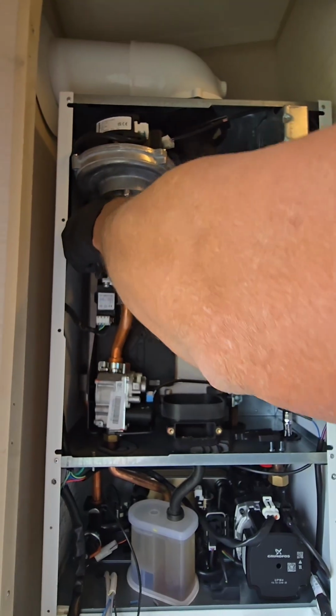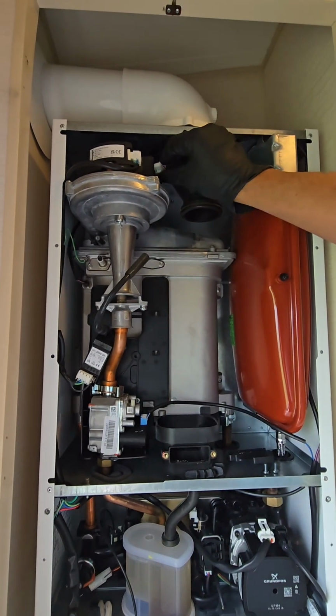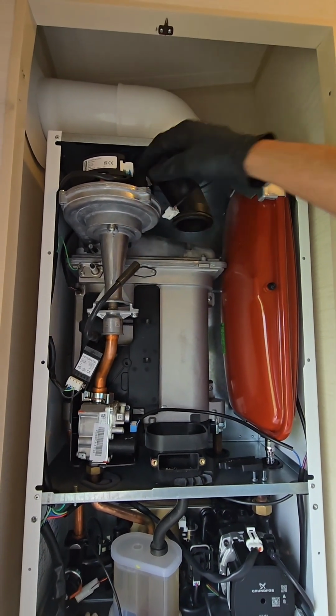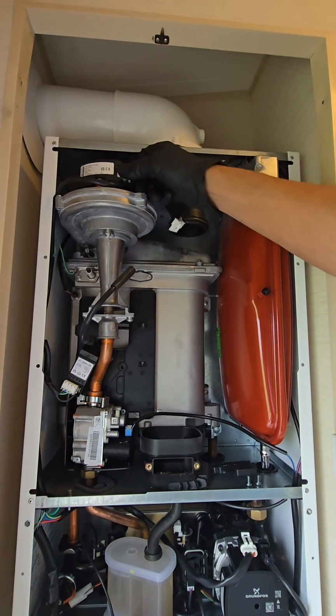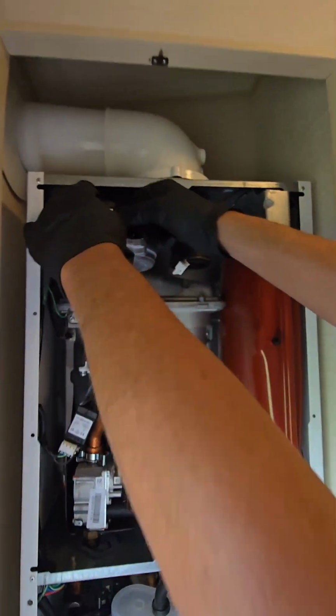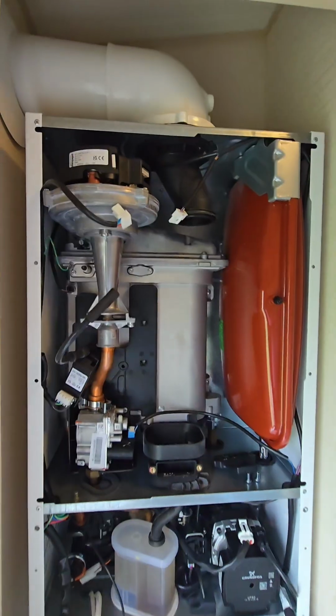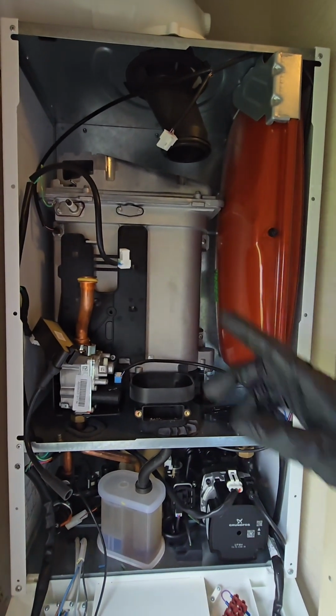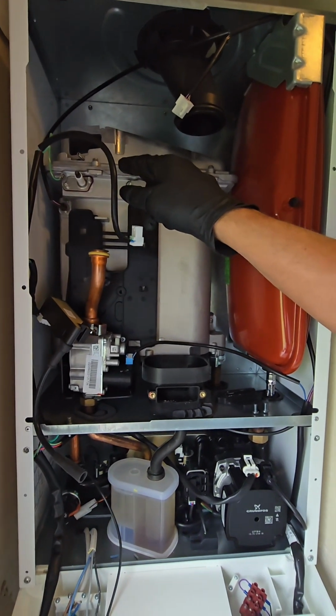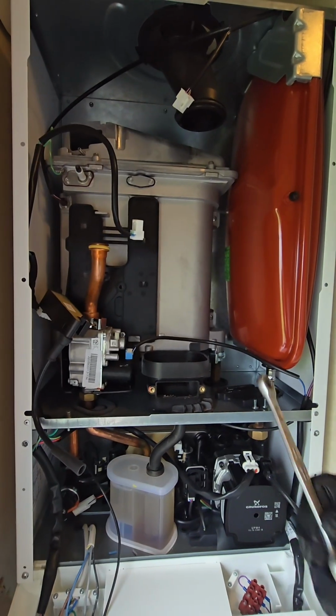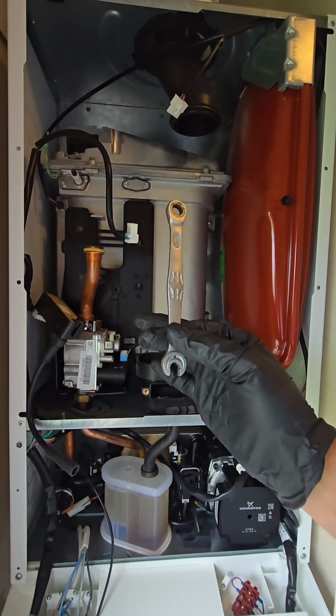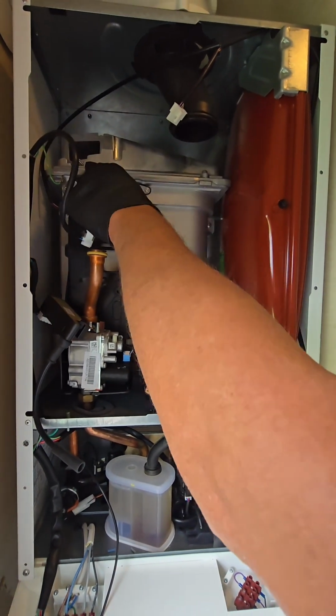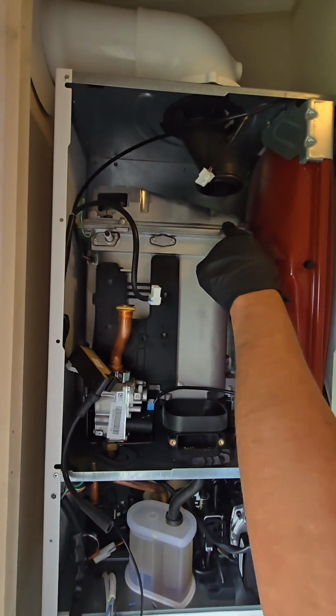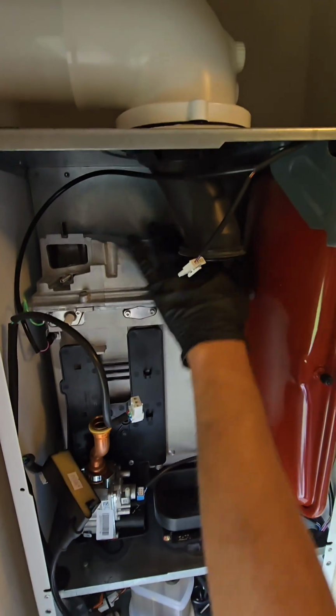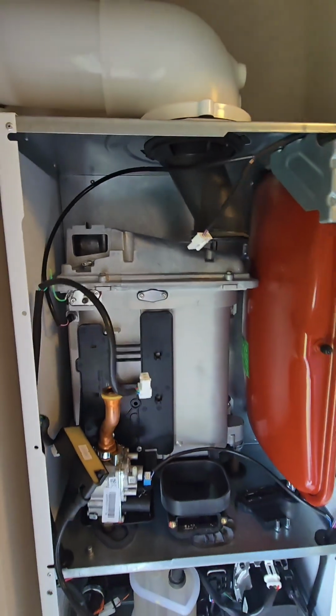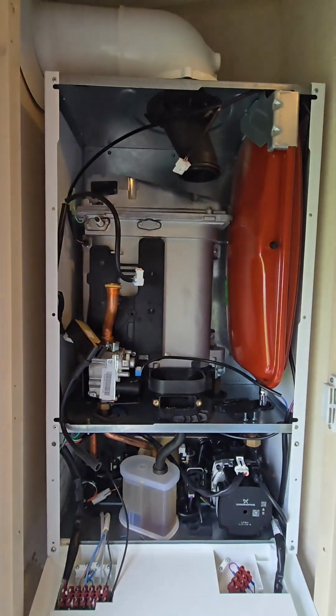Undo the lead from the electrode, undo the fan. This one can be a little bit tricky. For the next part we're going to remove the burner. I like to use a Wera Joker 8mm ratchet for this, and we have 2 small bolts at the front and 2 larger bolts at the back. All 4 of these will need to be removed.